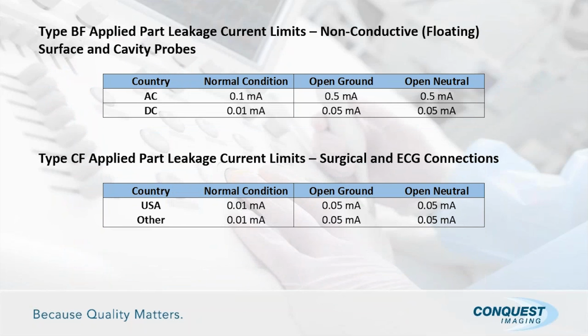There are two types of probe that are associated with ultrasound. The BF, which is a body floating type probe, is less restricted when you talk about the conditions. In a normal condition, you want to have 0.1 milliamps or less. When you open the ground, you want it to stay below 0.5 milliamps. And as you open the neutral, you'll want it to stay below 0.5 milliamps.